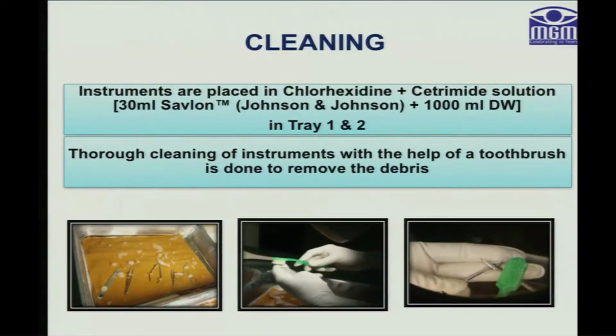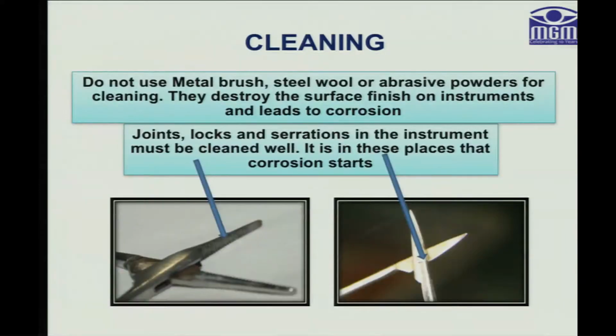Thorough cleaning of the instruments is done with the help of a toothbrush to remove all the debris. We should not use metal brush, steel wool or abrasive powders for cleaning, as they destroy the finish on the instruments and may lead to corrosion. Special attention to the joints, locks and serrations in the instruments must be given and cleaned well, because these are the places where corrosion starts and debris may accumulate.